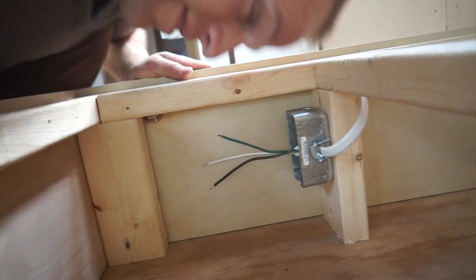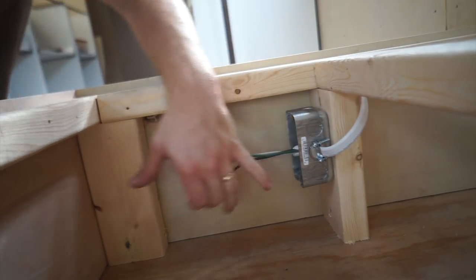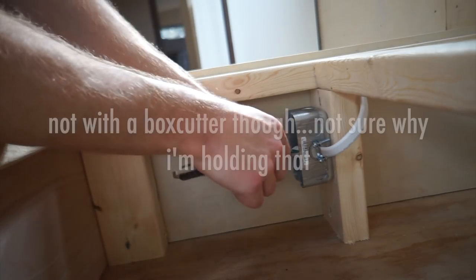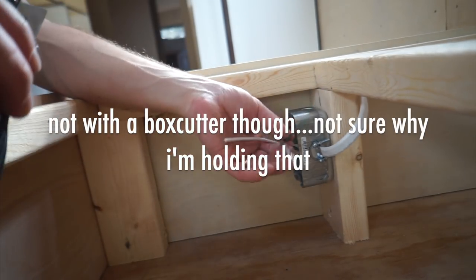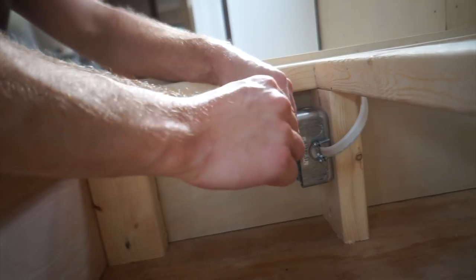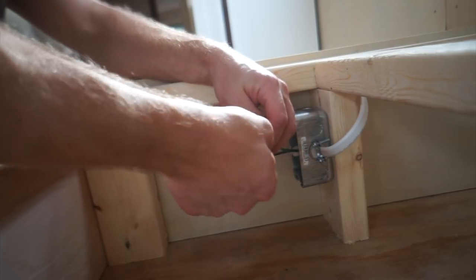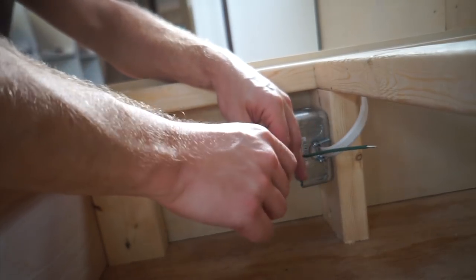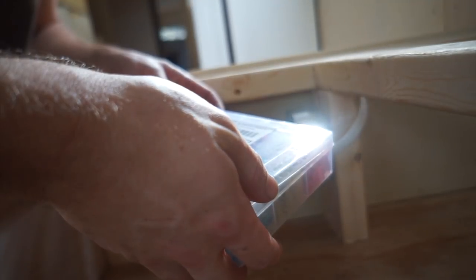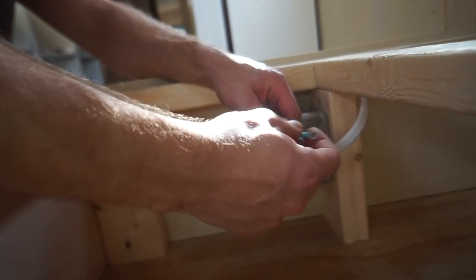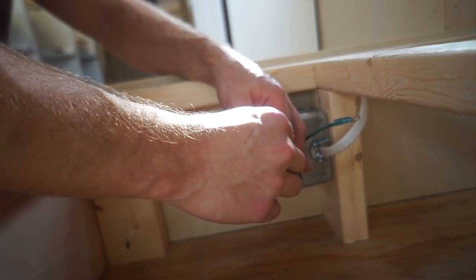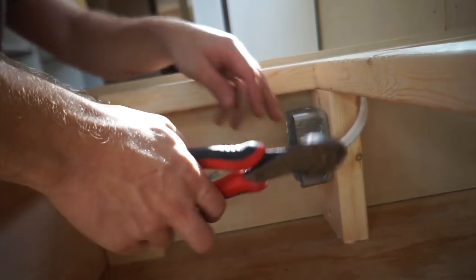Okay, so I'm going to show you how I'm wiring these outlets. First of all, I use about this much cable and then I cut off the sheathing so that I've got my bare wires. And I give each of them a little twist to help them stay together during the next part. And then I take each shrink wire connector kit. One of these on the ground, one of these each on the hot and the neutral. And then I crimp them.